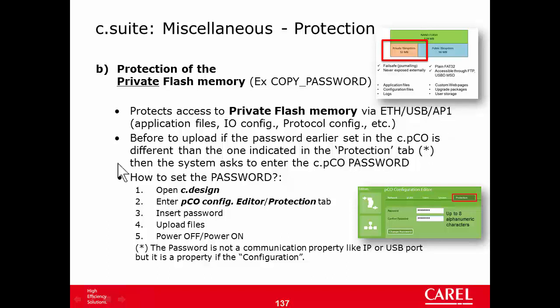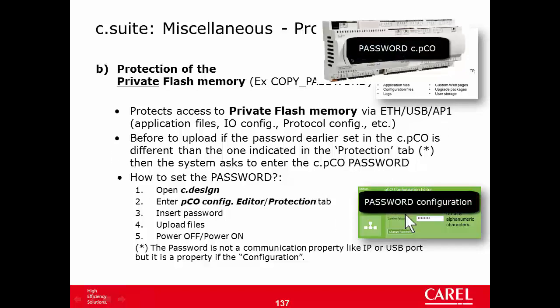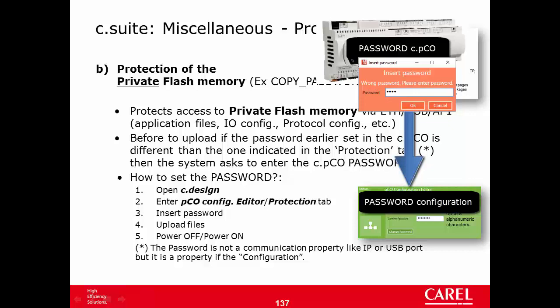The concept is simple. There is a password in the c.PCO controller and there is a password in the configuration — the application you want to upload. So when you are uploading an application, if the password in the c.PCO is different from the one in the configuration, then the system asks for the password of the c.PCO controller. If you insert the correct one, the upload continues. If you insert a wrong password, the upload is aborted.